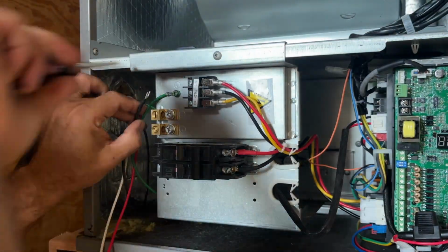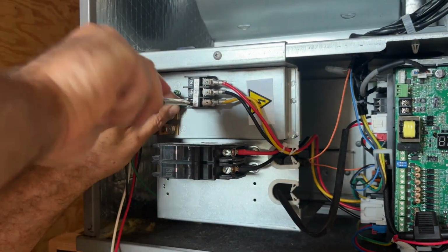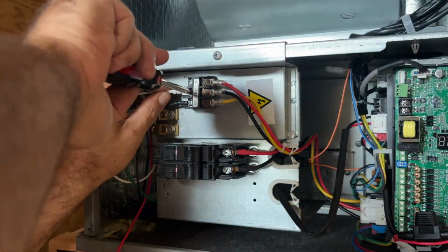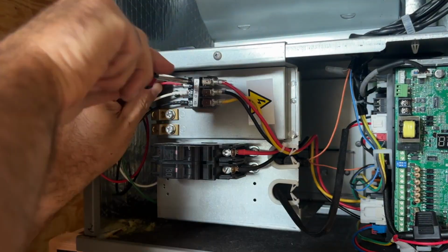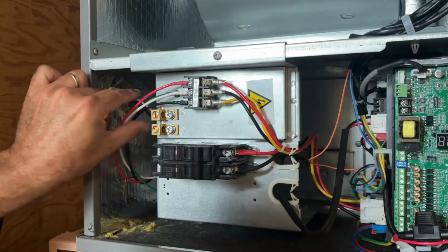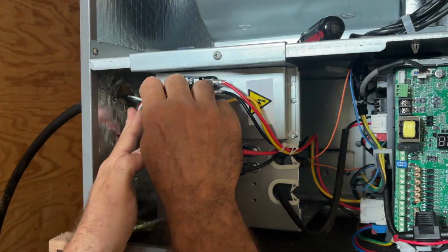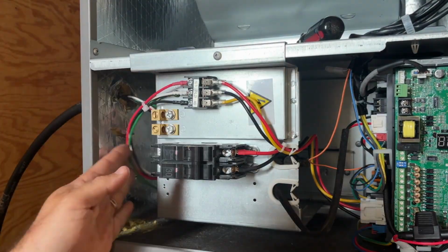Full disclosure here, this wire connection should probably be switched on the inside as well. I don't have line of sight to the external disconnect from the outdoor unit to the indoor air handler. Probably should have a switch here, but I don't.